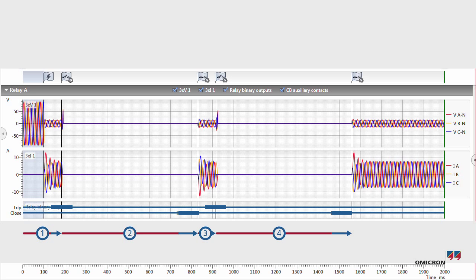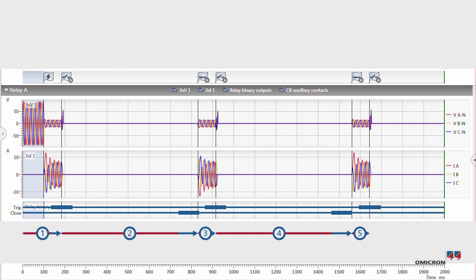Now the relay issues the final trip command and goes into lockout. RelaySimtest opens the breaker for a third and final time. With a final iteration, RelaySimtest verifies that the relay does not show any new reactions.